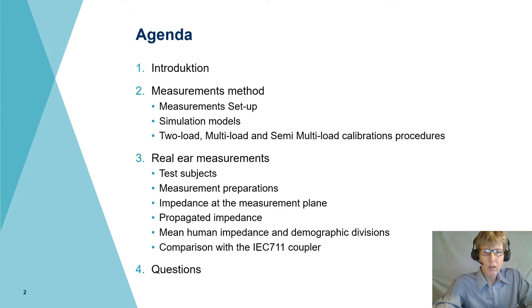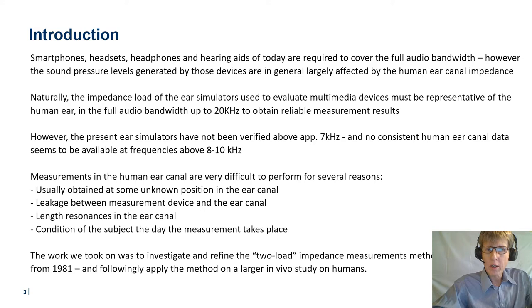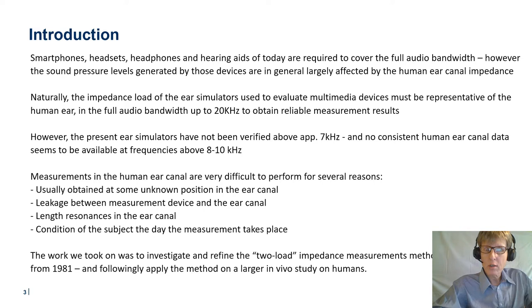Most smartphones, headsets, headphones, and hearing aids today are generally largely affected by the human ear canal impedance. Therefore, the impedance load of the ear simulators used to evaluate multimedia devices should be representative of the human ear in the full audio bandwidth to obtain reliable measurement results. However, the present ear simulators have not been verified against humans above approximately 7 kHz, and no consistent human ear canal data seems to be available at frequencies above 8 to 10 kHz.